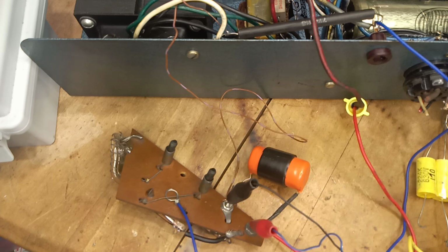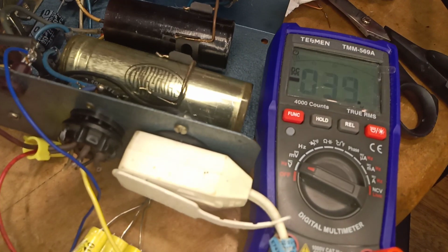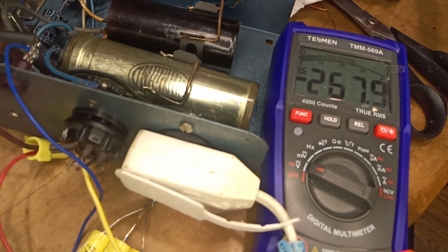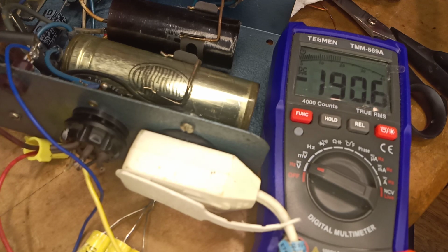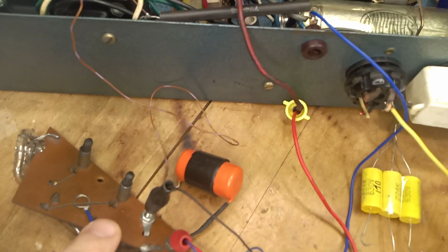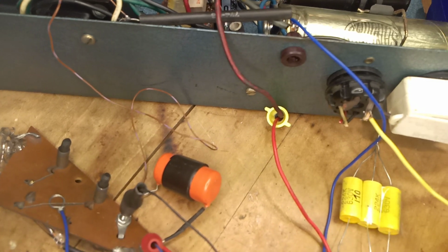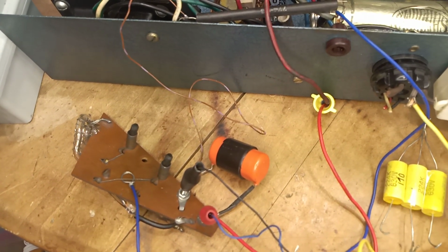So I'm going to turn this off. Some of these machines have an internal resistor. This one does, a 470K resistor that drains down the capacitors. As you can see, it takes quite a while for the voltage to drop down. So always check the voltage first. If you're going to make any readings on the terminals, you want to short those out first before you do any ohmmeter readings, because you can destroy your meter.